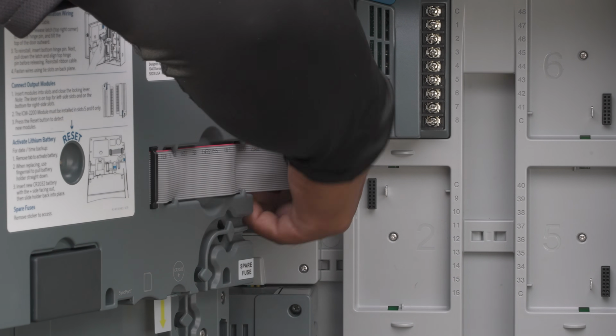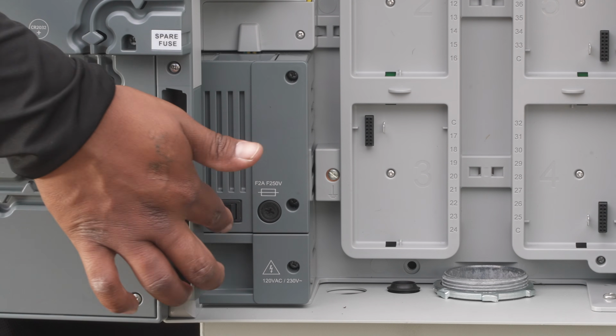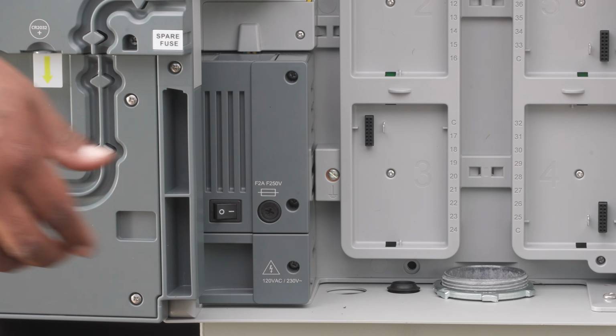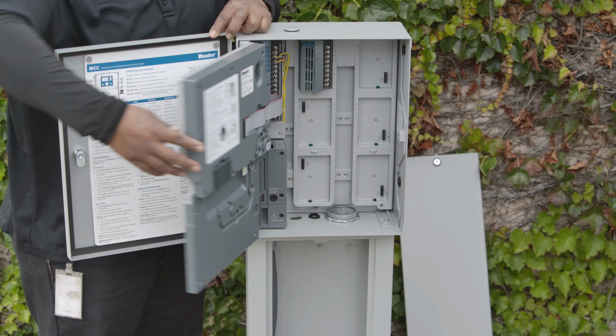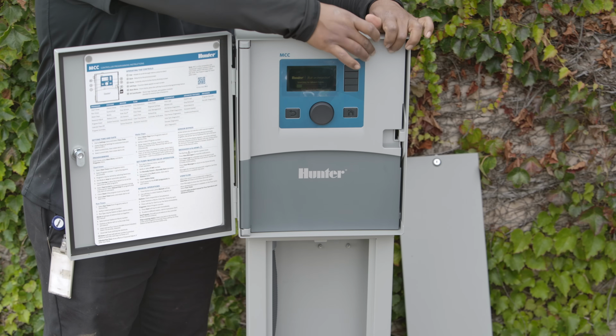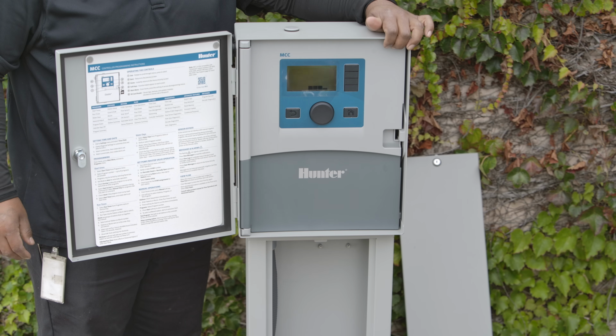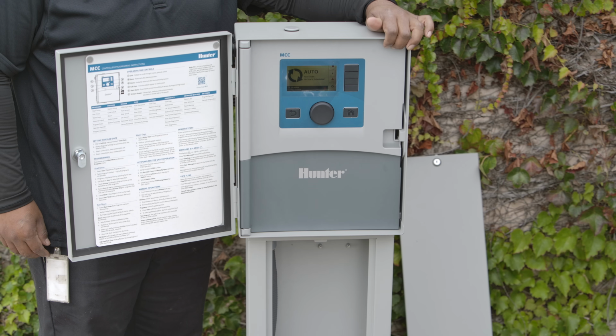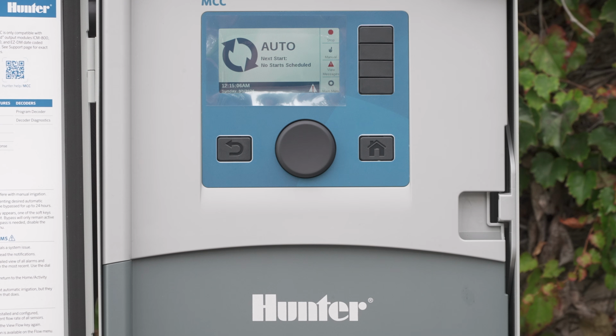Reconnect the face pack ribbon cable and remember to turn on the internal power switch. The controller display should light up and go through its startup sequence. It's normal to see a flashing error symbol after connecting the controller to power. The controller has detected that power was disconnected after it was tested at our factory and has logged this power loss event.